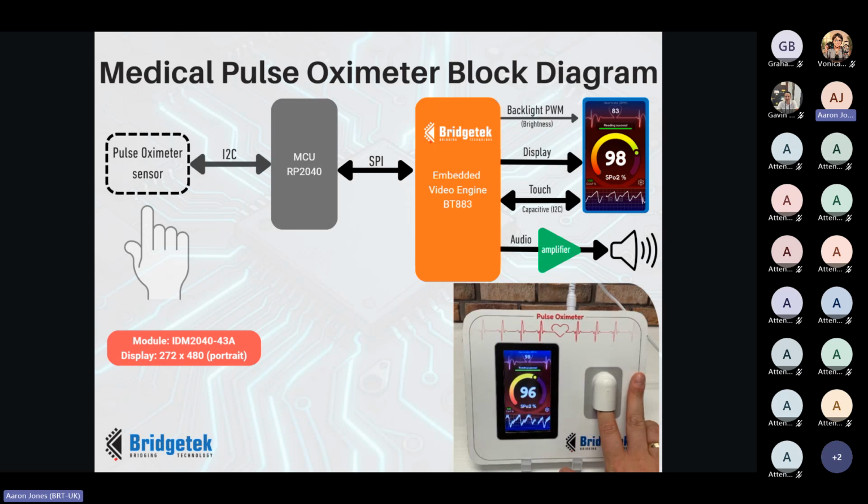For example, we have an ARC widget here to give us our current SPO2 level. It's looking good at 98 on this screenshot, but 96 on the video, so might be on the edge there. But then the Eve renders the graphics for us, showing a scrolling graph of the live LED readings and updates the ARC widget with our current oxygen level. Touch is also enabled on this demonstration for a small settings menu, allowing us to rotate the screen if desired and turn on and off an audio beep, which is also incorporated into this example using Eve's inbuilt audio synthesizer.